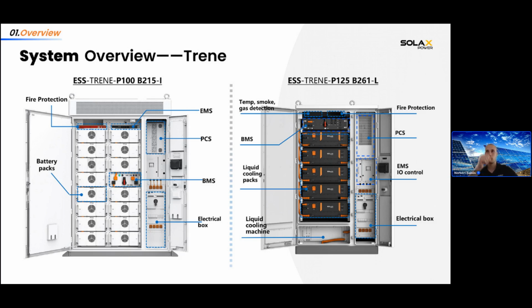And for the liquid cooling version, you can actually see it from the naming of the product. When you check ESS TRENE and P100 and P125, it refers to the AC power that it can give you, and the B215 and the 261 is the capacity of the battery. The I and the L refer to I as the air cooling version and L as the liquid cooling version. But you can already see it in the picture on the right that you have liquid cooling cells. It's much more effective than the air-cooled version.